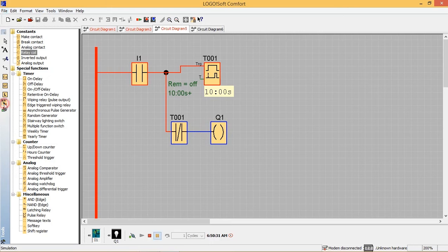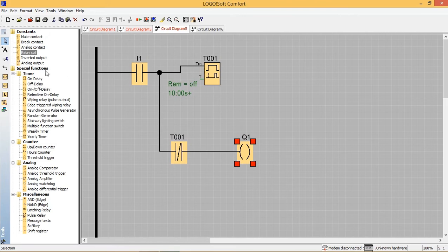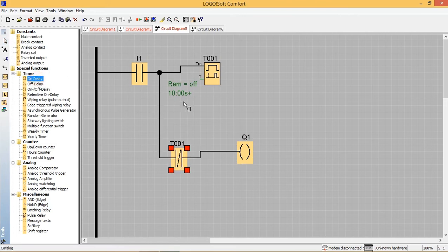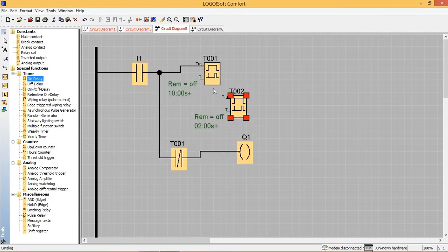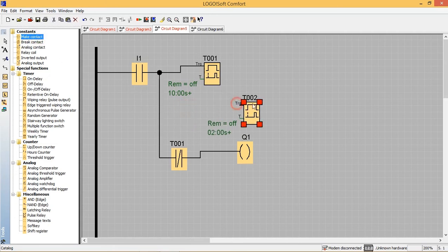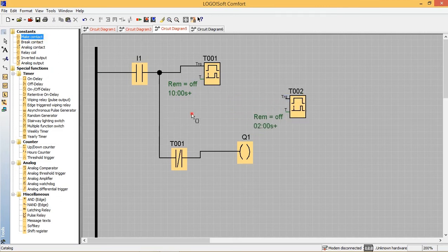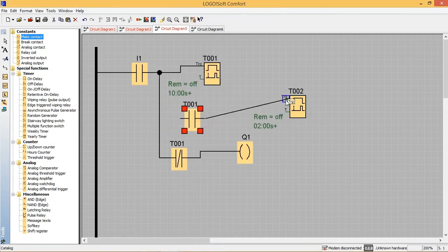I'm making changes in the same diagram. 10 seconds is already set. Now we need to add an extra 2 seconds, so I'm taking one more timer for setting a 2-second delay. I've taken an ON-delay timer. Once timer 1 completes 10 seconds, timer 2 needs to count 2 seconds. I'm taking the T01 feedback and connecting it to timer 2.